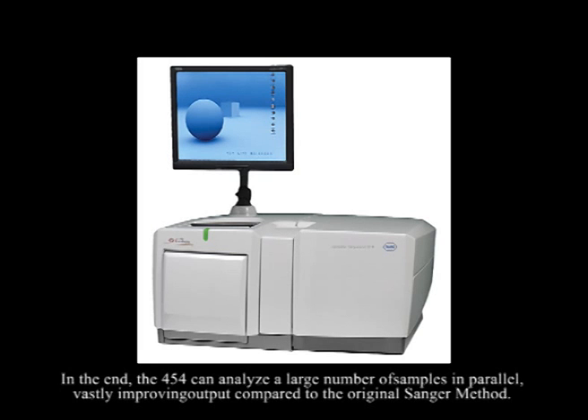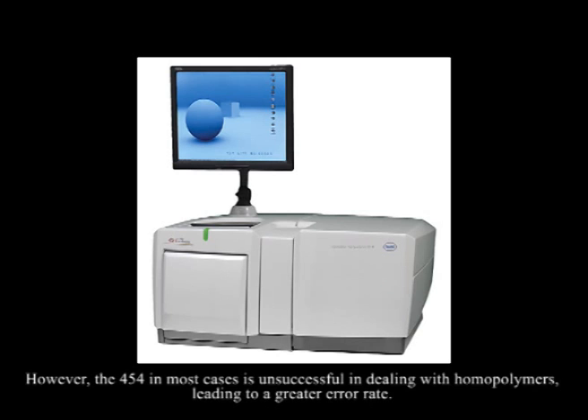In the end, the 454 can analyze a large number of samples in parallel, vastly improving output compared to the original Sanger method. However, the 454 in most cases is unsuccessful in dealing with homopolymers, leading to a greater error rate. It is also more expensive to sequence per base than some of its competitors.